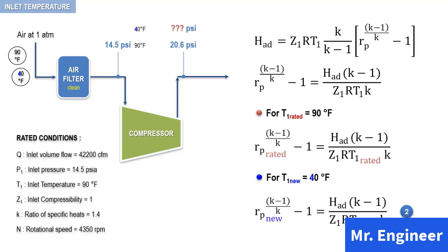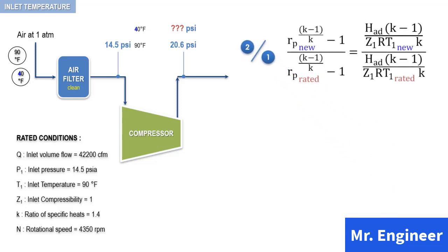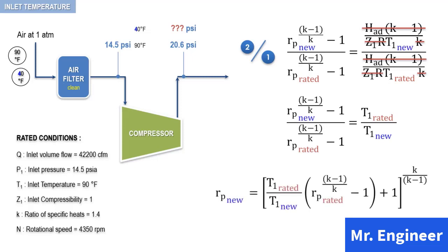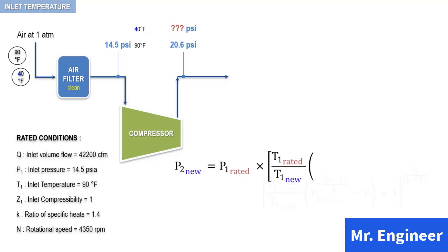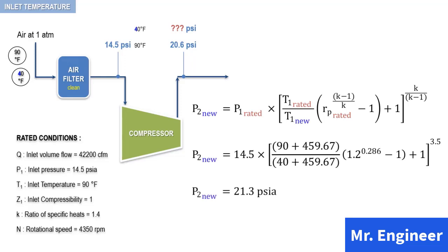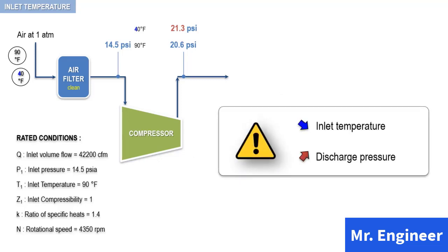For a change in inlet temperature only, we can write the following for the rated inlet temperature and for the new inlet temperature. Dividing the second equation by the first will yield the following. Rearranging this expression gives the following useful relationship. Solving for the new pressure ratio, and since the new pressure ratio is equal to P2, the unknown new discharge pressure, divided by P1, which is unchanged, the new discharge pressure can be expressed accordingly. Substituting for the known values gives the new discharge pressure.